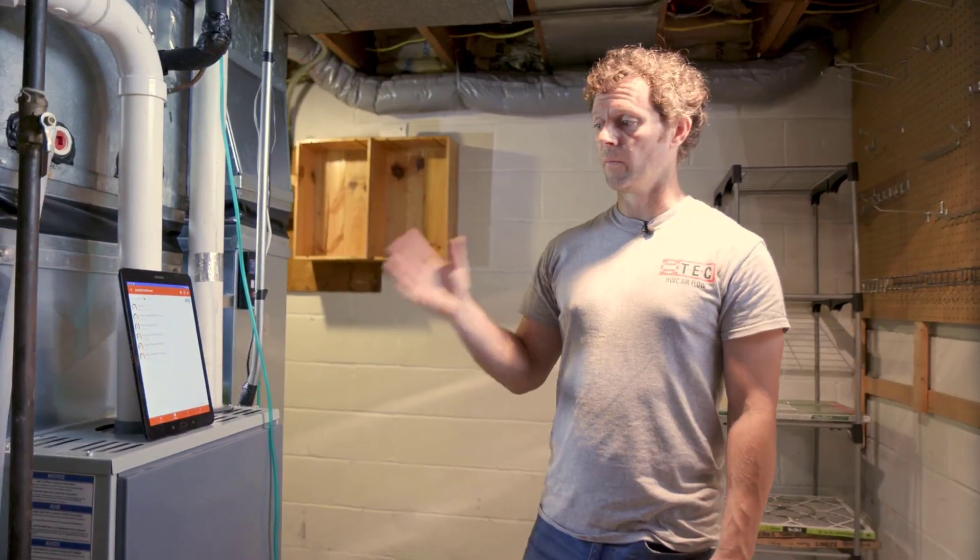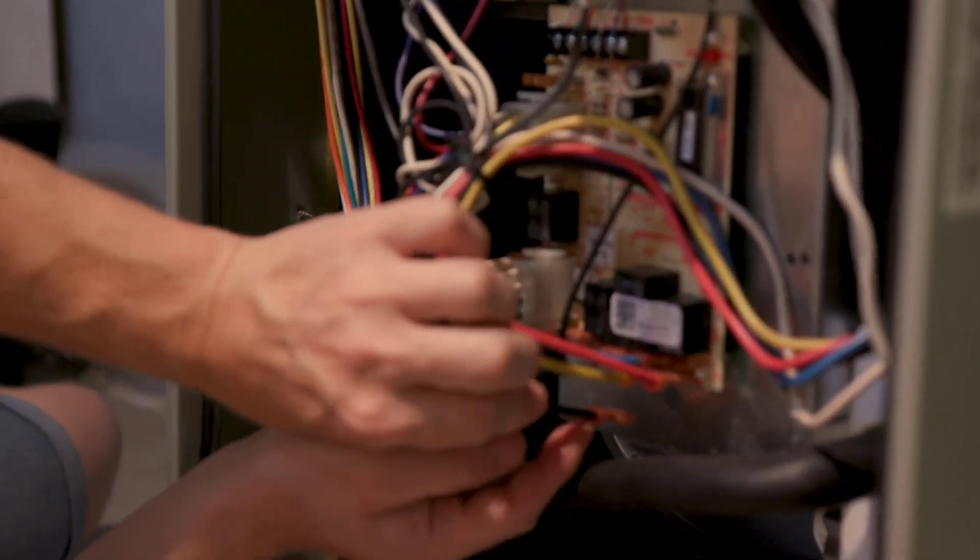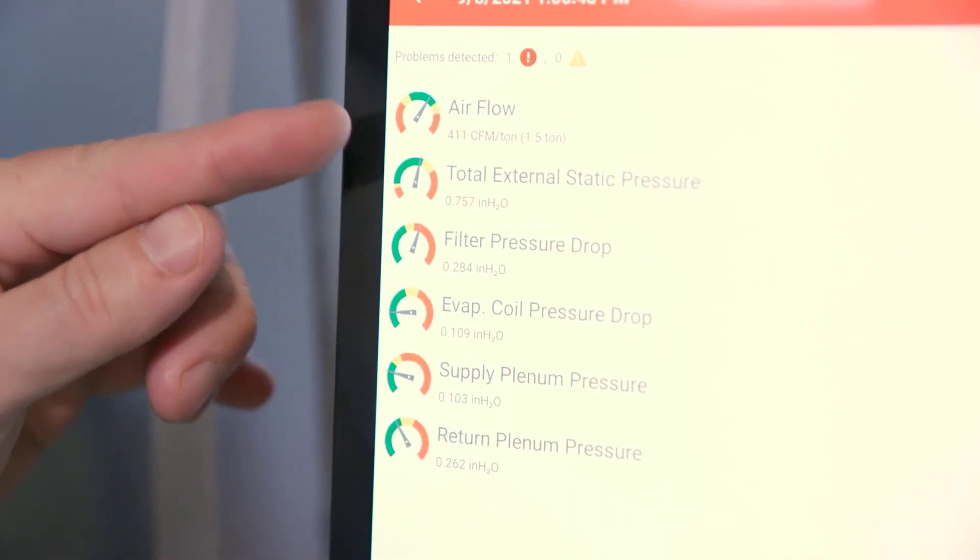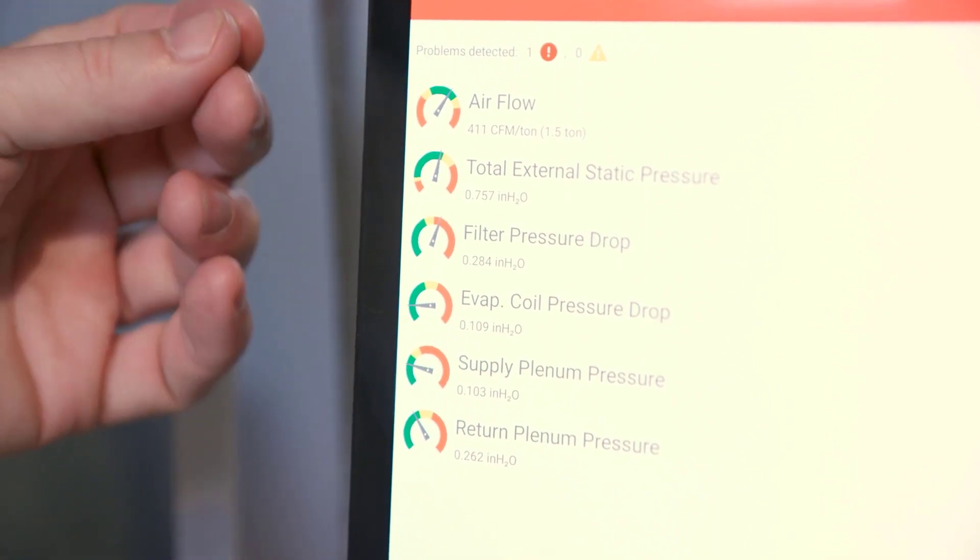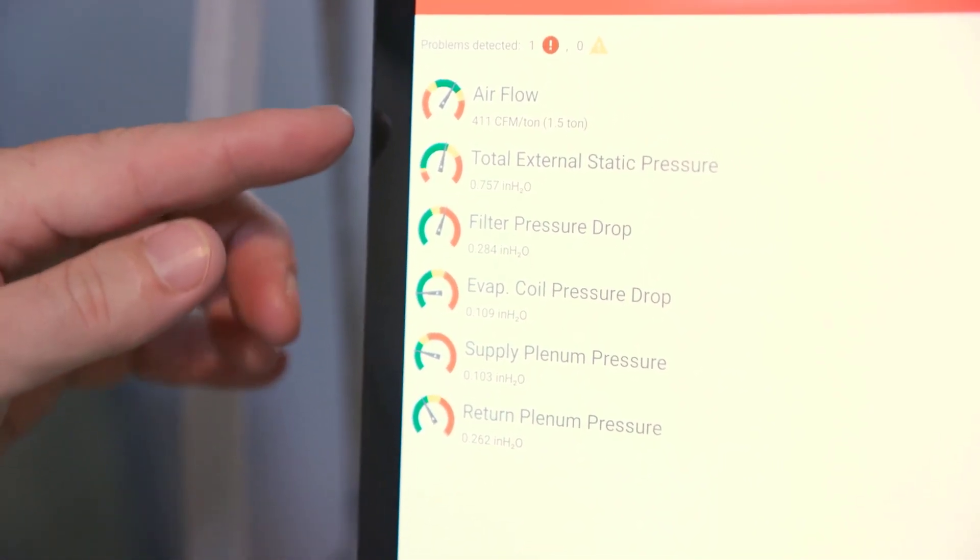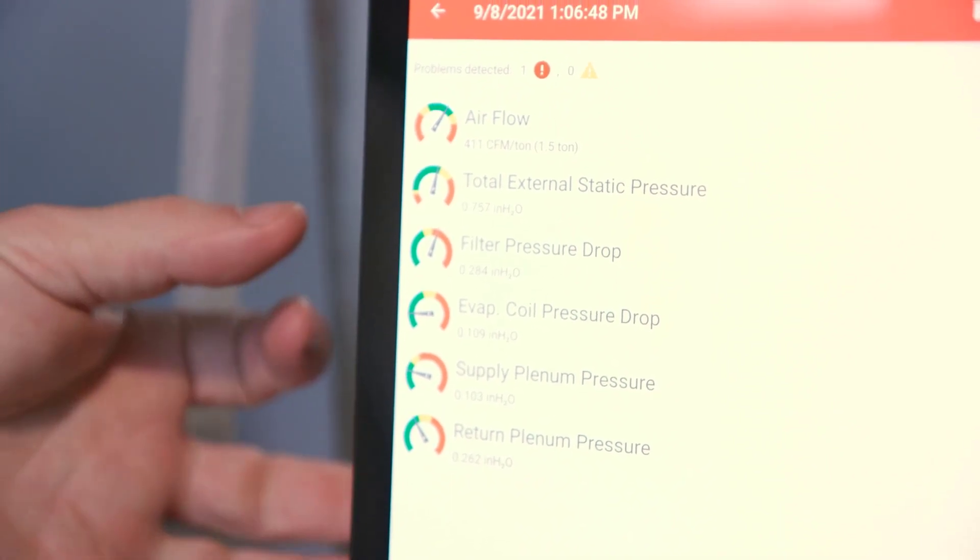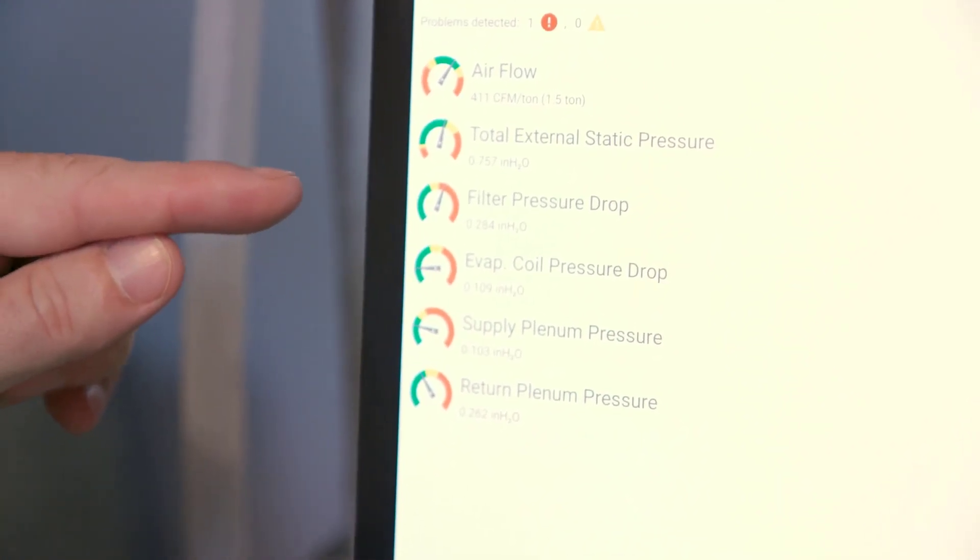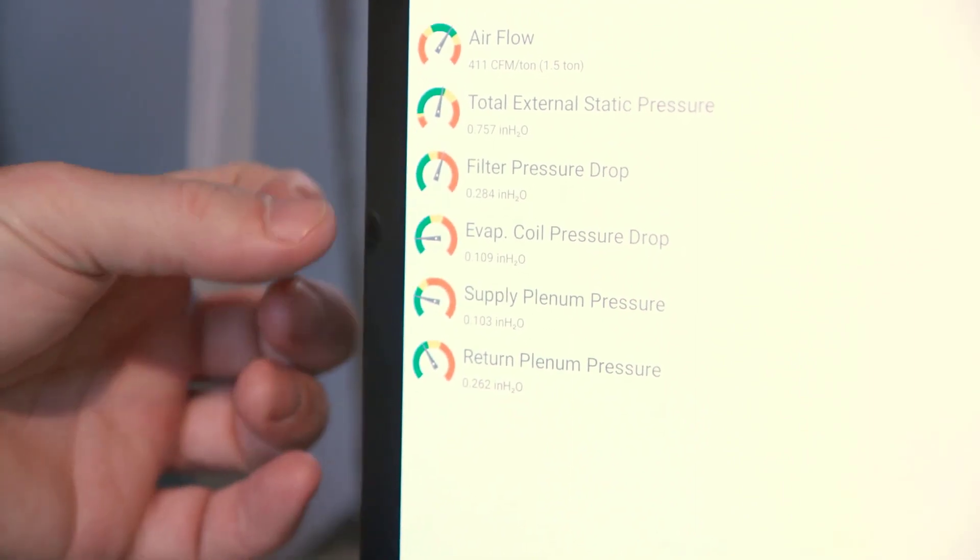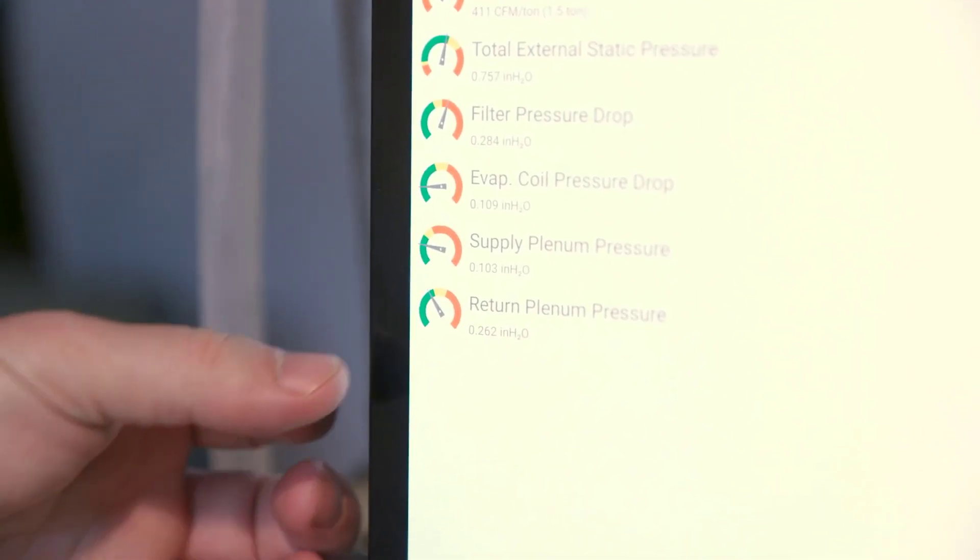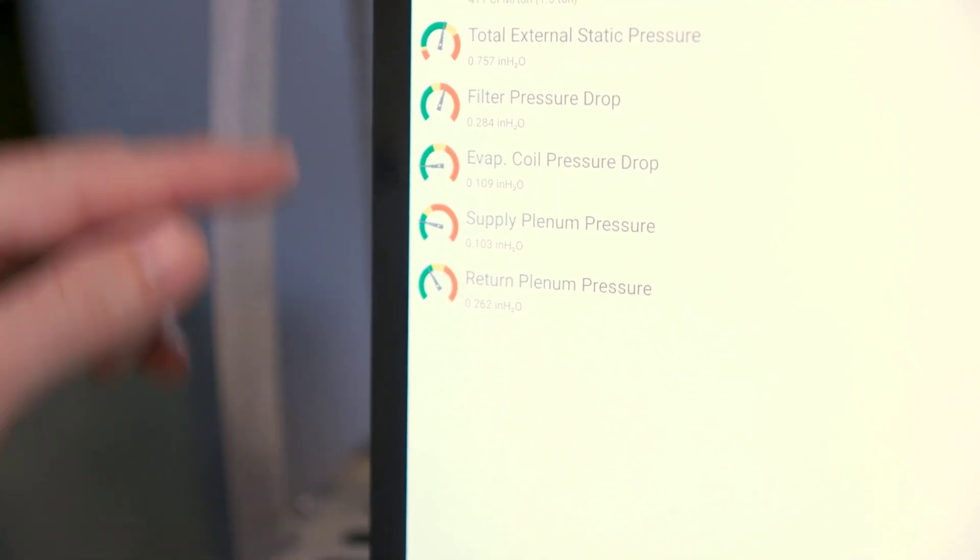So these are the results from the furnace in its existing setup. What we're going to do next is actually adjust the fan speed and redo the test. Our airflow is now in the green at 411 CFM per ton. Our total external static pressure dropped and is now in the green. We still have a high filter pressure drop. Our evaporative coil is still in the green. Our supply got a little bit better and return pressure actually got quite a bit better.